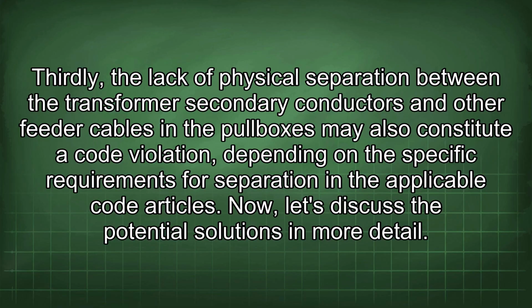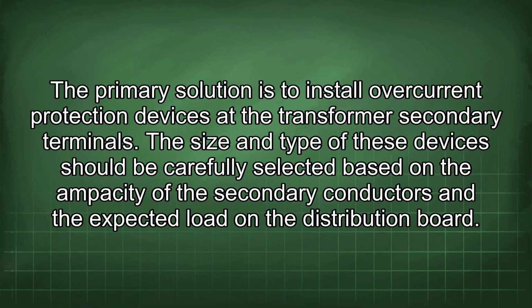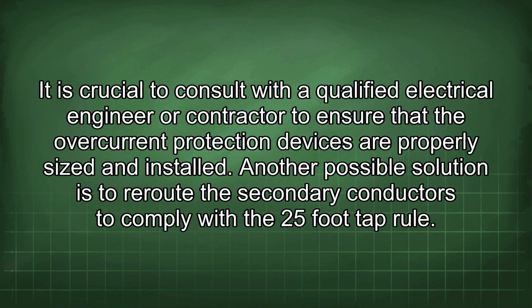Now let's discuss the potential solutions in more detail. The primary solution is to install overcurrent protection devices at the transformer secondary terminals. The size and type of these devices should be carefully selected based on the ampacity of the secondary conductors and the expected load on the distribution board. It is crucial to consult with a qualified electrical engineer or contractor to ensure that the overcurrent protection devices are properly sized and installed. Another possible solution is to reroute the secondary conductors to comply with the 25-foot tap rule.